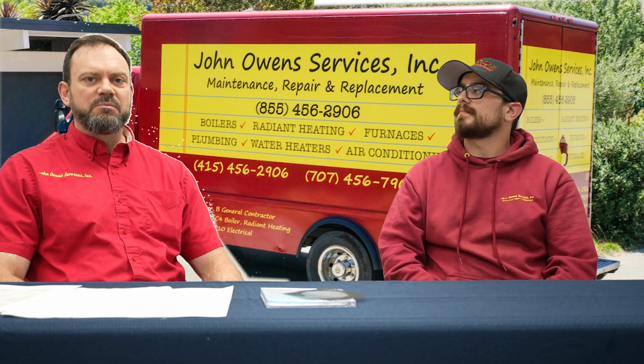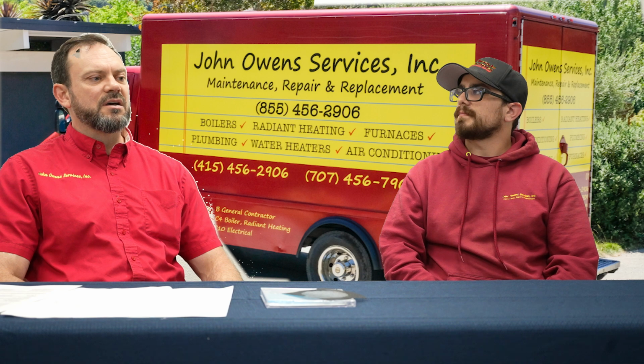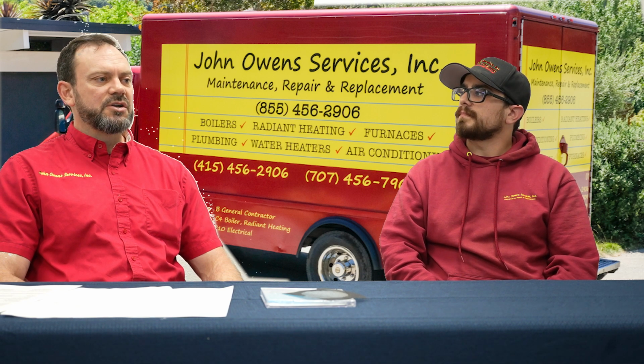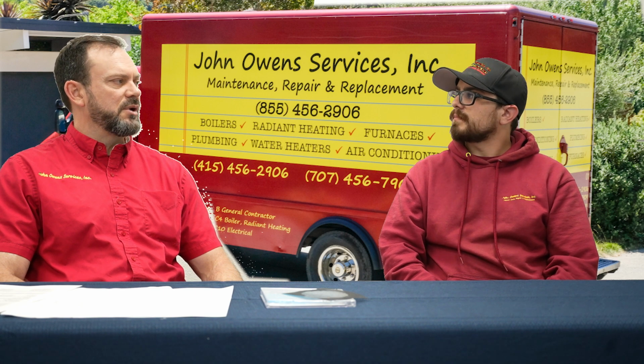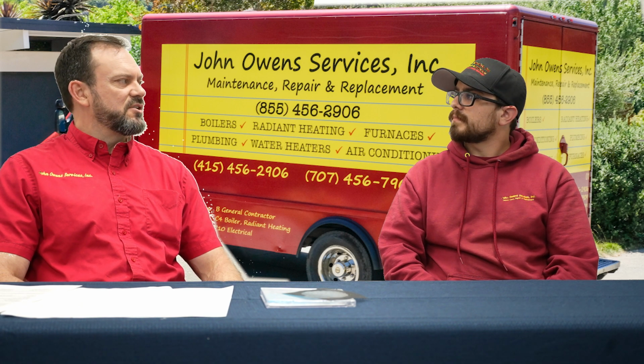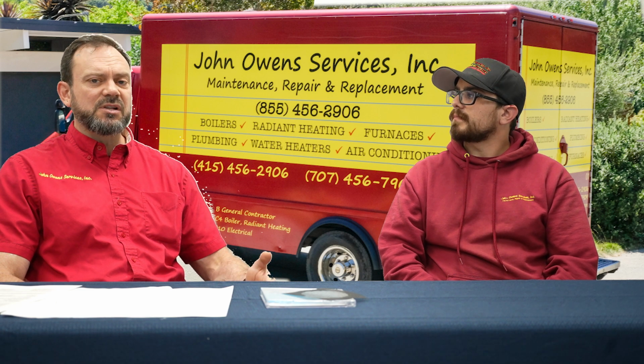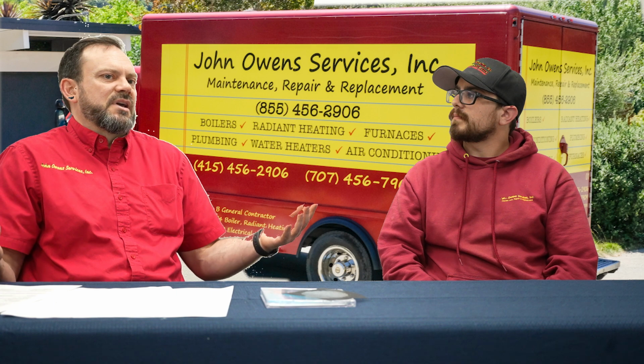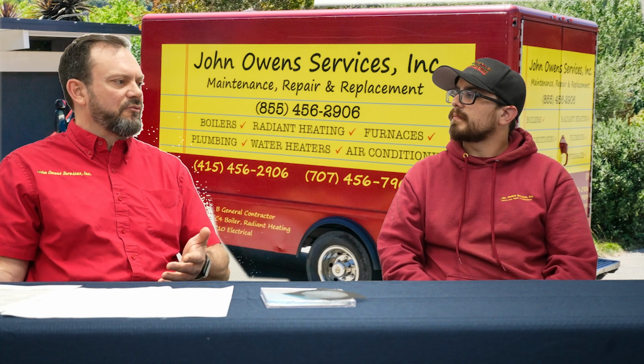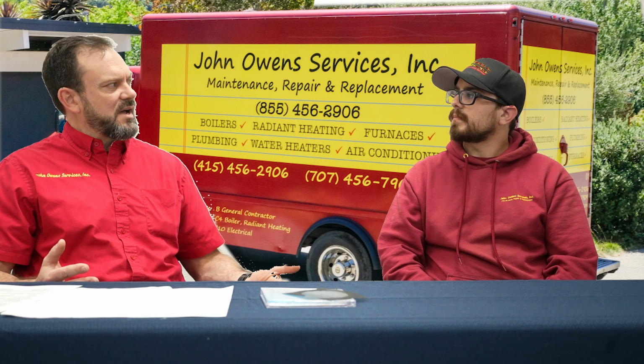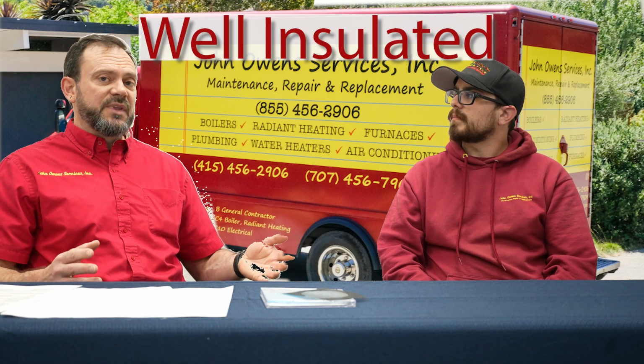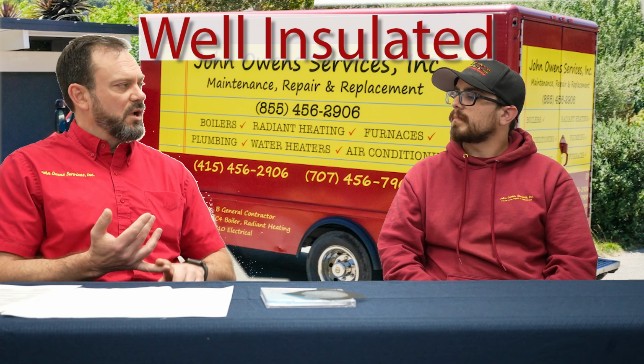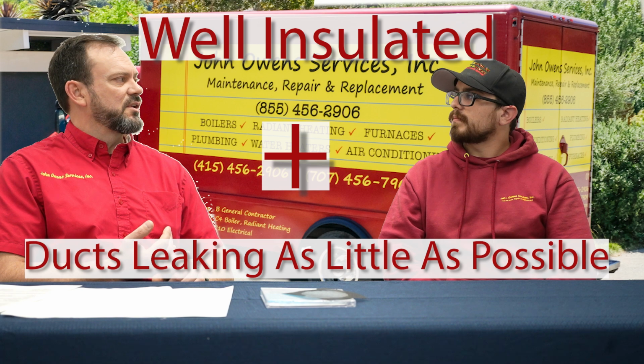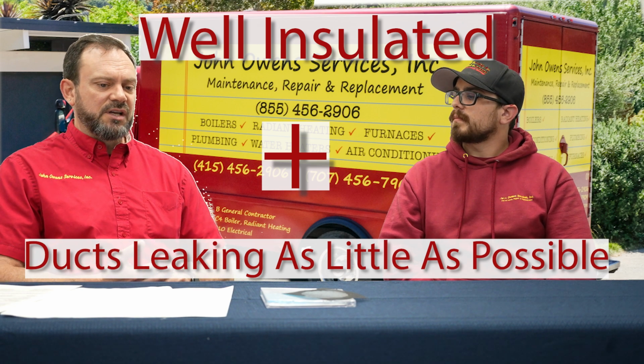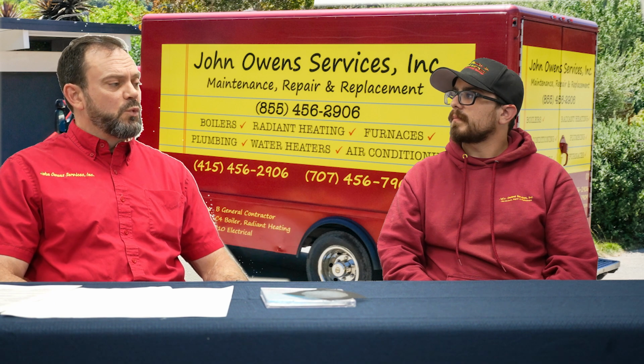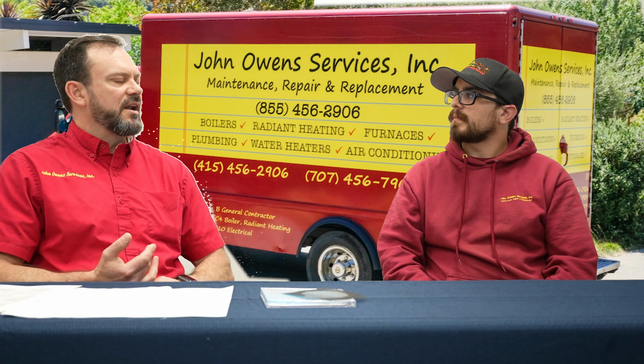But now we're talking about electrifying houses, we're talking about heat pumps, and we're talking about systems that need much higher efficiency ductwork for them to heat your house. I mean, we need to extract every BTU that we can out of these systems to properly heat a house, especially a larger house. The biggest heat pump I can get is 60,000. So if I'm going from a 100,000 BTU furnace to a 60,000 BTU heat pump, then I better make sure that our house is, A, well insulated, and B, my ducts are leaking as little as possible. So your duct leakage is a really big component of efficiency and health in the house.